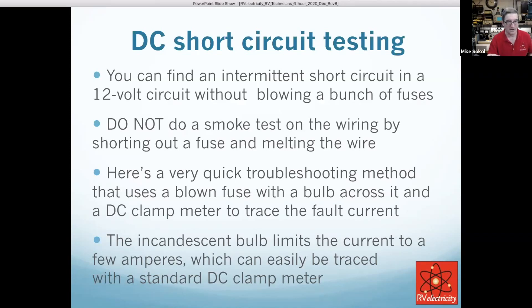When they got tired of blowing fuses, my boss would take the fuse, wrap it in foil, and stick it in there. He said we're going to do a smoke test. The wires would start getting hot and smoking where the current was, and when you found the spot where it stopped smoking, that's where the short was.